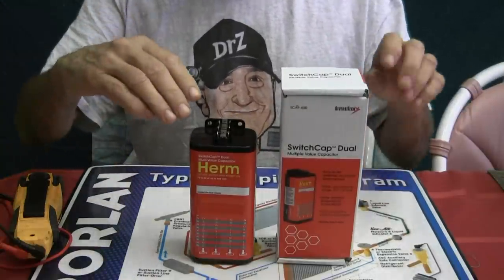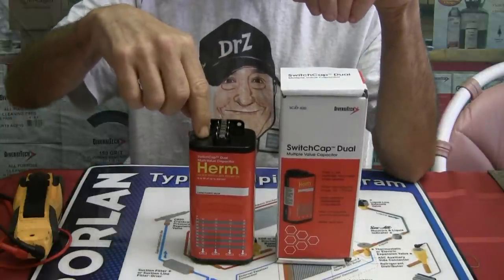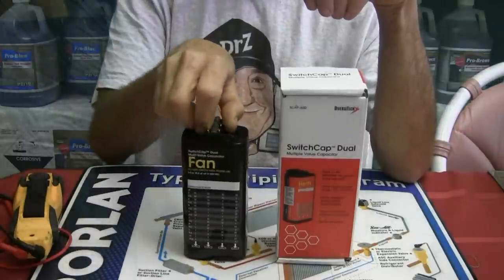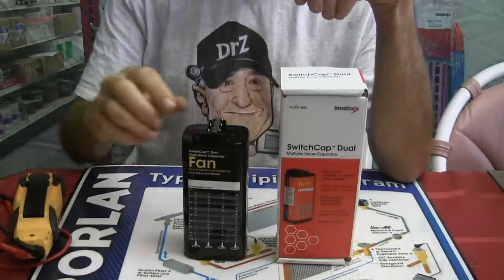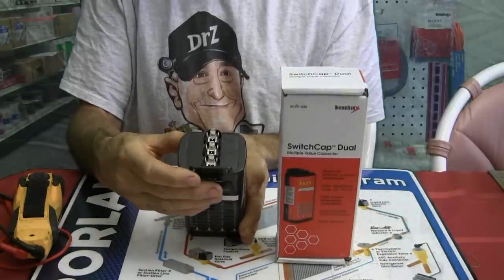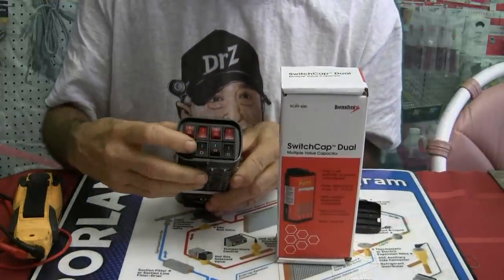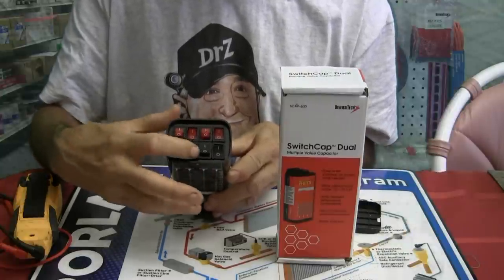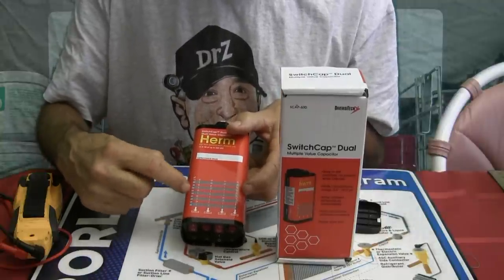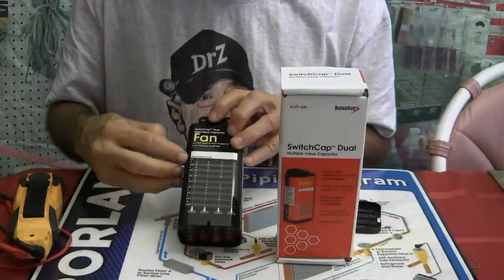Today I want to show a run capacitor here that is sold by Diversitech. This is a multi-value dual capacitor. This side is for Herm, as in for your compressor, and the other side here would be for your fan. Here are the taps, right up here as you would normally see on any dual run capacitor. On the bottom you'll see where you can adjust your values for both your compressor and your fan, according to this particular chart right here, which shows the different values it can be set up for.